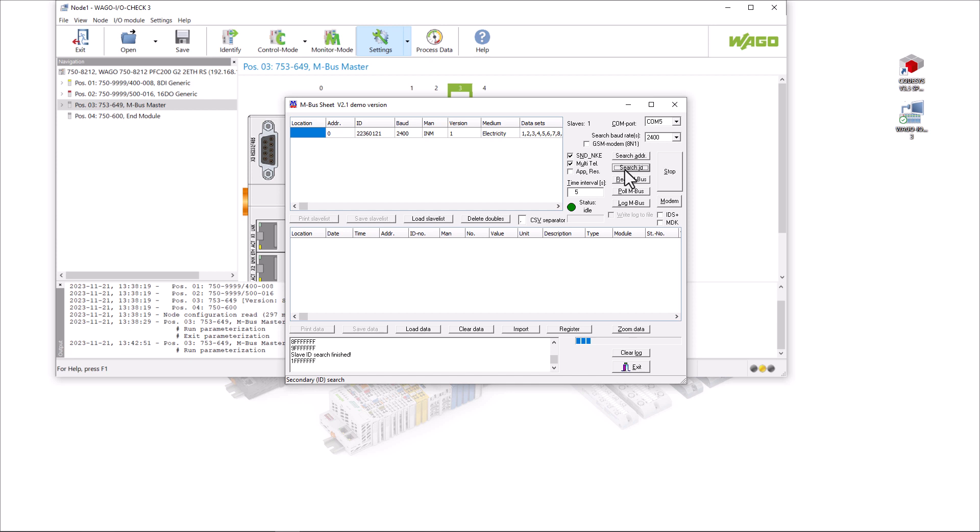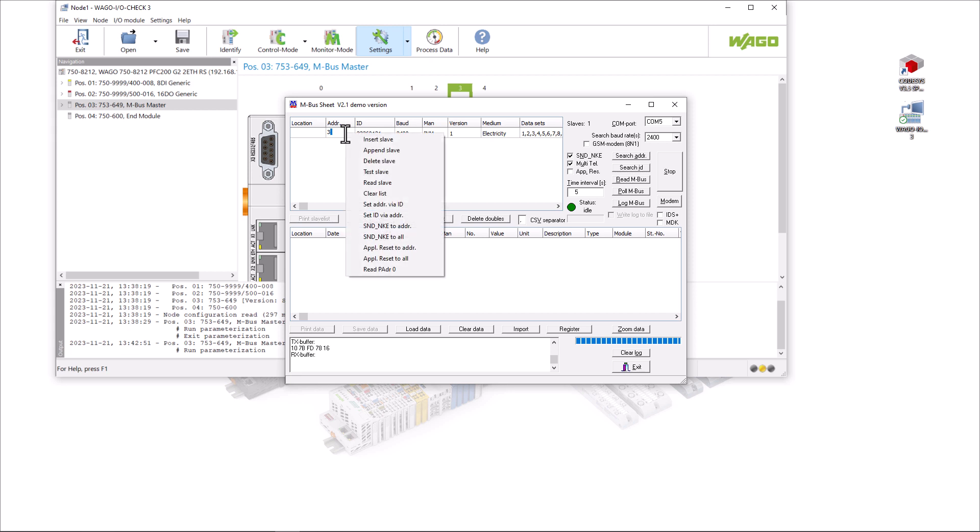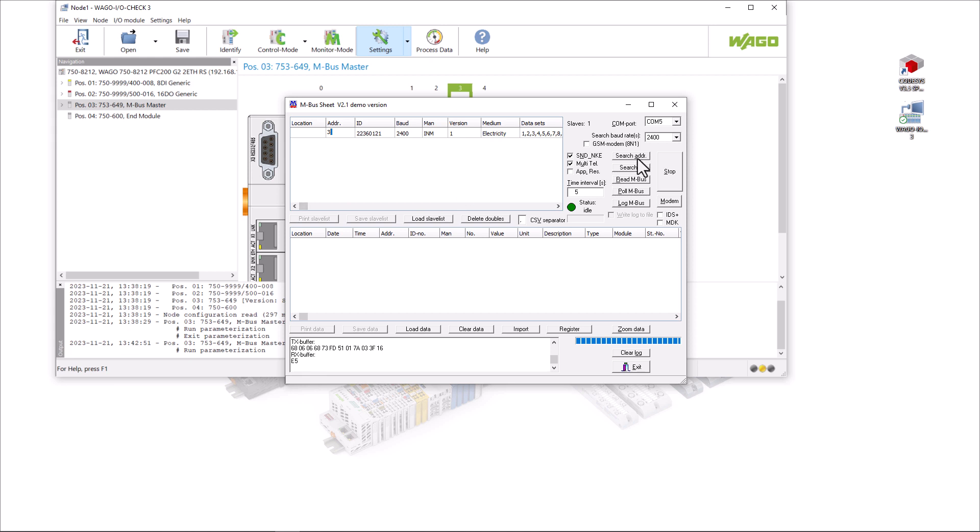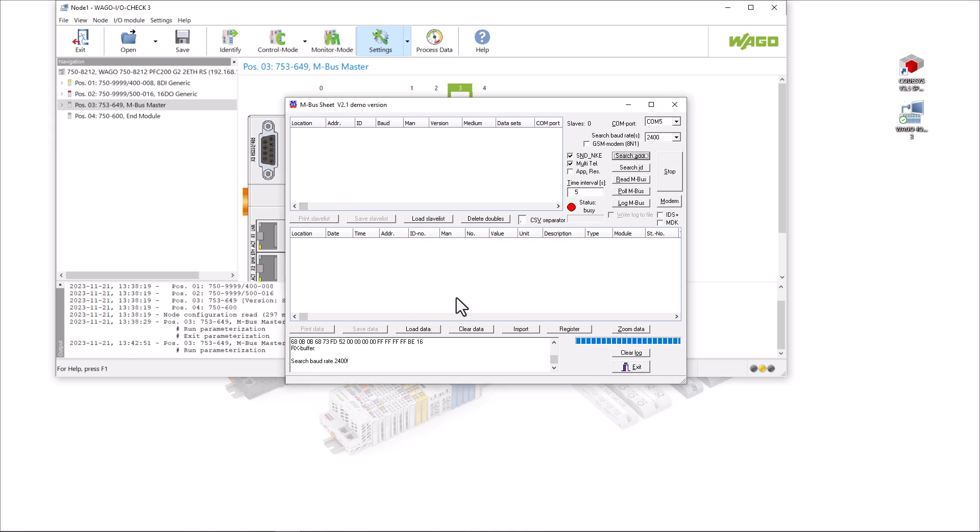As the primary address is not queried in the ID search, a 0 is always displayed here. Now we can assign primary addresses in the range from 0 to 250, for example the 3, and link the new primary address to the device ID. When searching for primary addresses, we now also see the assigned address so we can identify any multiple assignments.